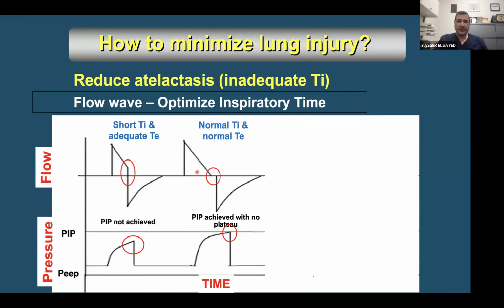You need to see the I time is enough for the inspiratory flow to reach 0 before the beginning of expiration, and the PIP reaching the preset PIP. But we are using the hybrid mode now, so you have to be sure that the measured tidal volume is reaching the preset tidal volume.